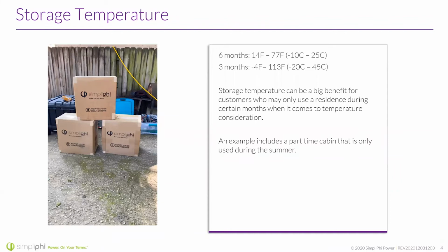Storage temperature is a little different. We rate that differently. So if it's stored, this could be a huge benefit if you maybe are only using the residence during certain months, maybe warm months. Oftentimes I see this with people with cabins where they have battery storage. It's a great way to store the batteries, even though the temperatures are going to get lower than you typically would want for charging and operating.